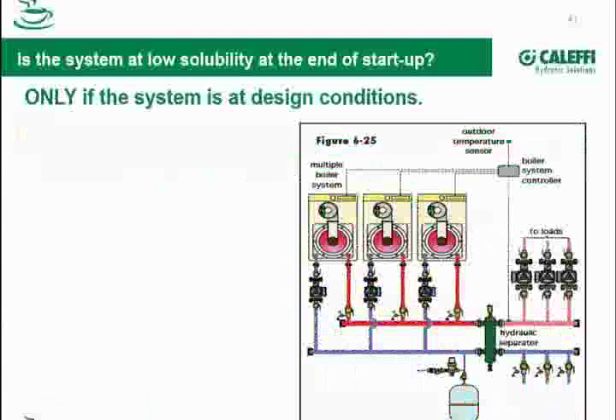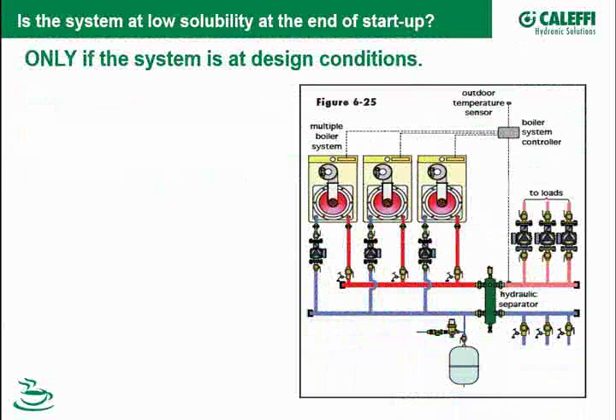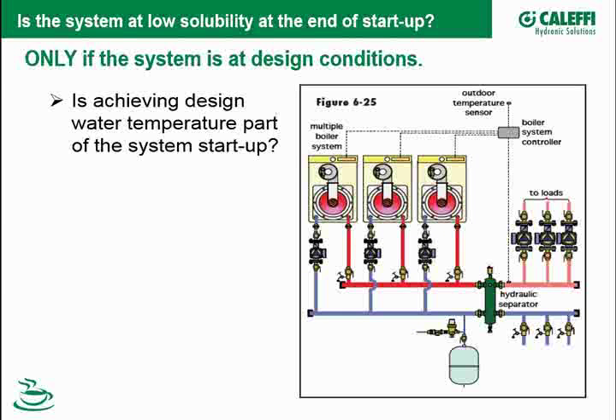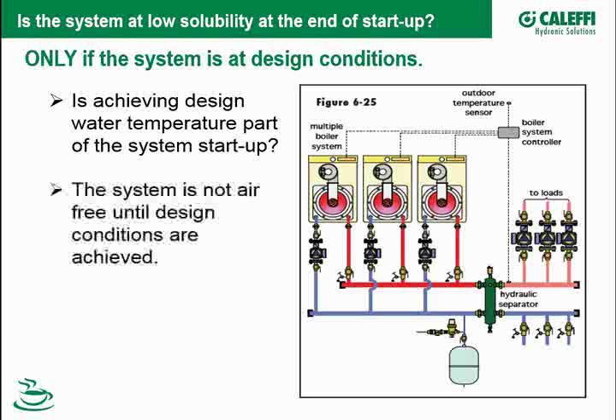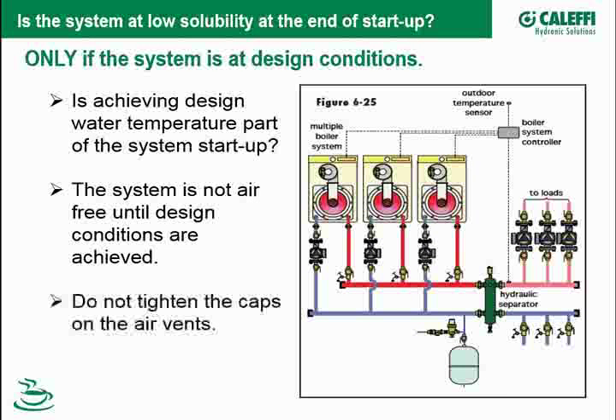A couple of procedural things: the system is only air-free when it gets to design temperature and pressure. The question that always comes up is a start-up question: did you bring that system up to design conditions on start-up? Did you achieve the design water temperature? If not, as the water temperature starts to increase, the system is going to continually let out air, because the system is not going to be air-free until it's at design temperature.